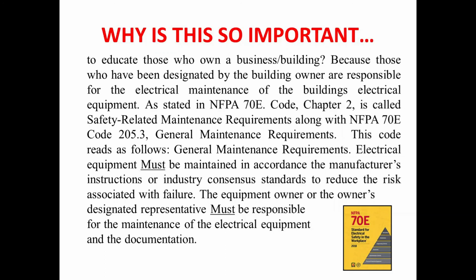As stated in NFPA 70E, Code Chapter 2 is called Safety-Related Maintenance Requirements, along with NFPA 70E Code 205.3, which is General Maintenance Requirements. Notice that the word is requirements, not options, requests, or recommendations. These are requirements. The code reads as follows.